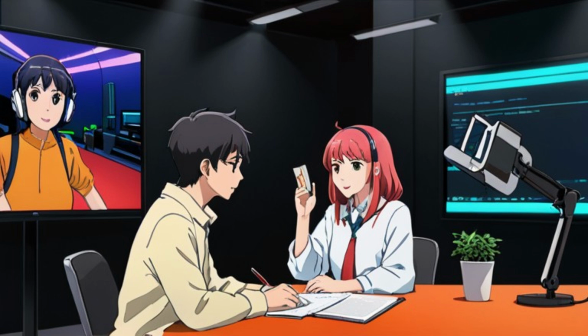And what if the parameters we measure don't match the expected values? Initial adjustments should only be made after validation with the technical management or maintenance manager. Any modifications must strictly adhere to the manufacturer's specifications and with all necessary safety precautions taken. It's crucial to remember that in a complex system, any change to one setting can have unforeseen effects on other parts of the system.